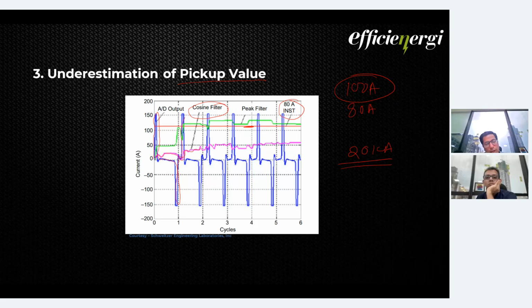There are some advanced relays wherein, instead of the cosine filter, you can use peak filters. So this green line is basically the peak filter value, which is taken from the peak filter output. Again, if you see, the peak filter is also very close to the pickup. So it is not guaranteed that even the peak filter will work in this scenario. So this is the third case where, because of CT saturation, a fault occurs but there is no tripping of the relay.